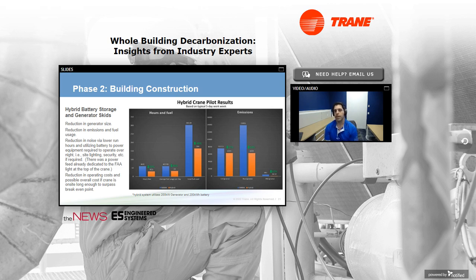That 200 kW generator combined with the battery can charge over time and build up to the power needed, then the batteries discharge along with the generator to provide that peak power, which isn't needed very often, considerably reducing the fuel and energy required. As you can see, emissions were 54% lower, and the cost of fuel and operating costs were also reduced.